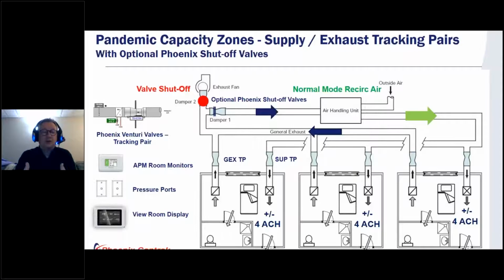And so this is a diagram look at what we were just talking about. Typically, your pressure is neutral for patient rooms, 4 air changes per hour. We were showing this diagram here with a tracking pair system, supply valve, and an exhaust valve. Again, exhaust tracking supply, maintaining neutral pressure, both applying the same amount of flow into that space, right? But then when we go into pandemic mode, we're going to open up the exhaust fan, turn it on, and we're going to shut off the fan to the damper to the air handling unit to stop all the recirculation, right?